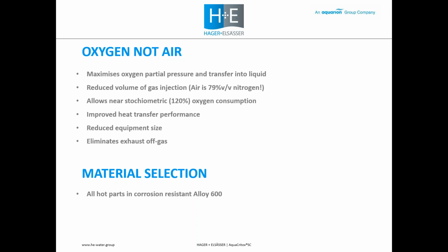So we're injecting only oxygen. This allows us to achieve approximately 120% stoichiometric addition of oxygen. If we were to use air, we would have very large volumes of nitrogen. Now, these volumes of nitrogen themselves have no impact on the overall reaction process within the liquid. However, they do mean that we have to inject larger volumes of gas, which is inefficient.